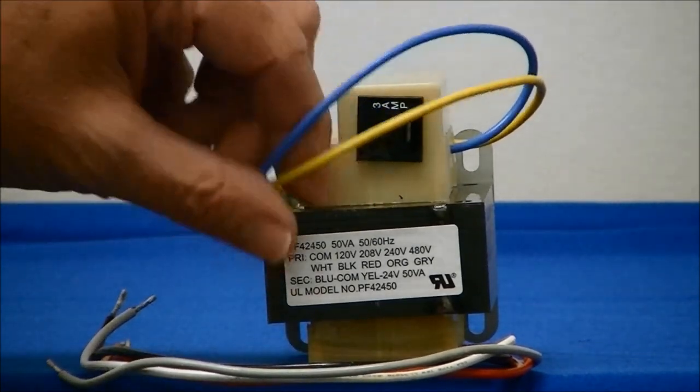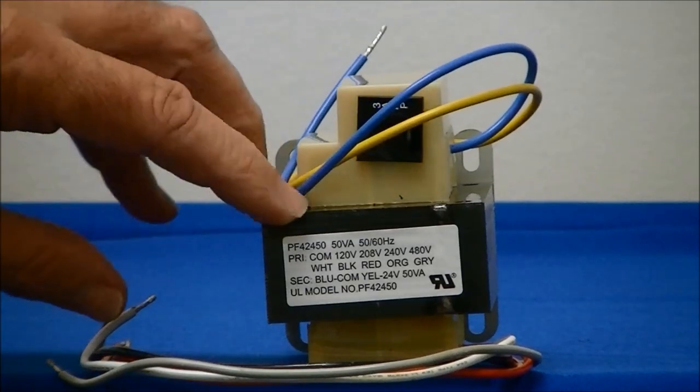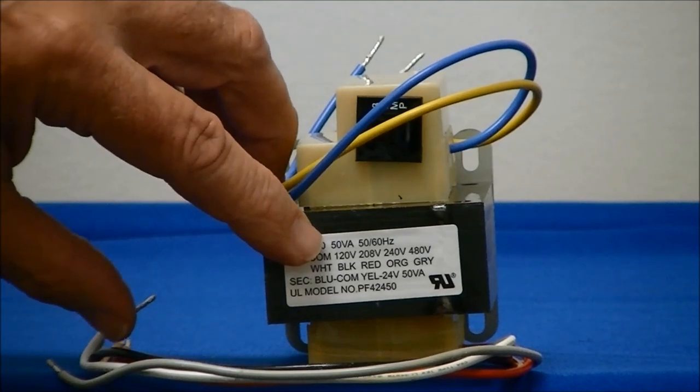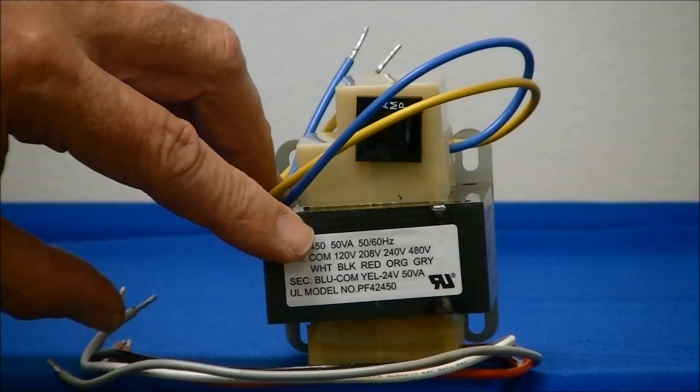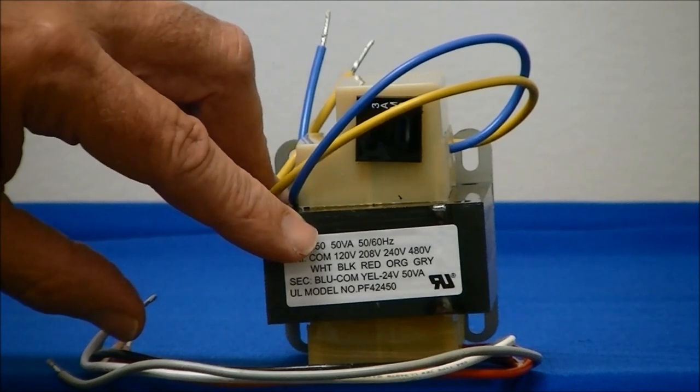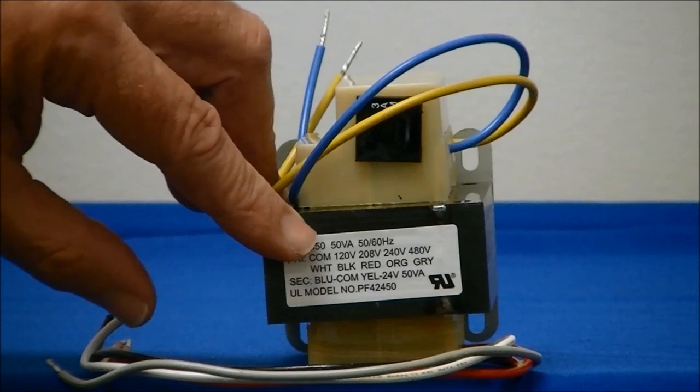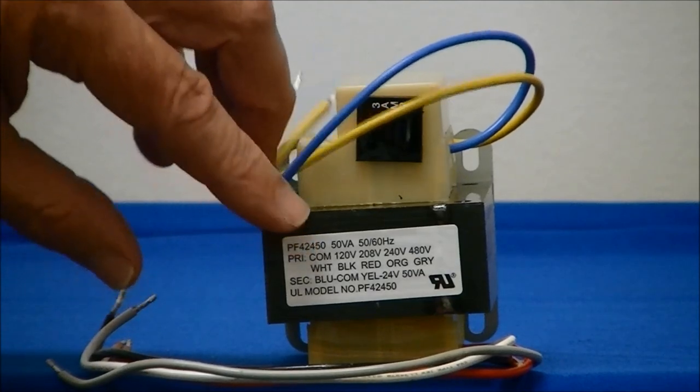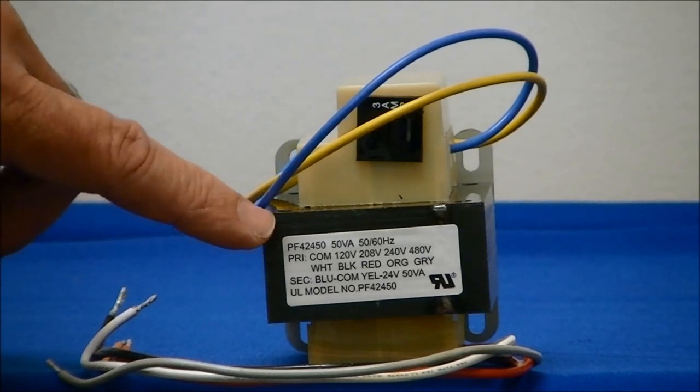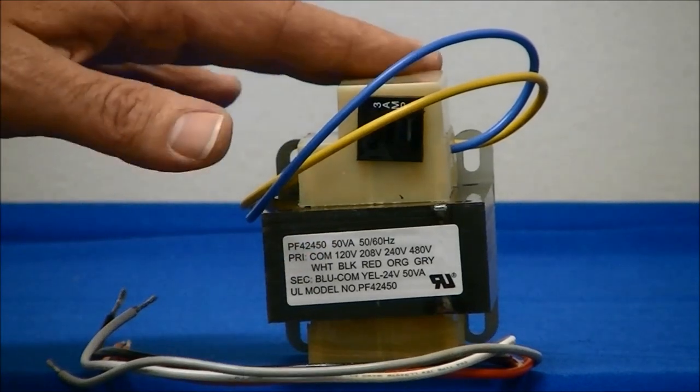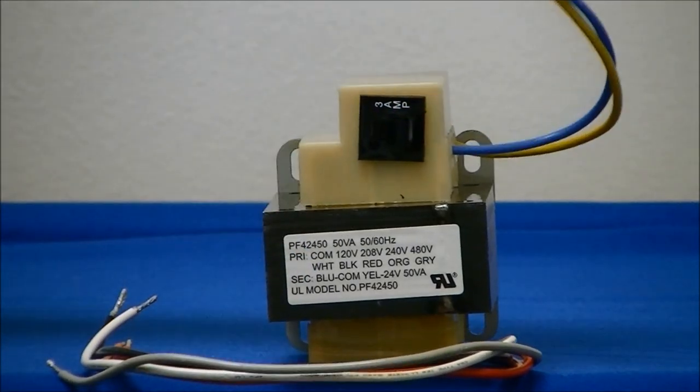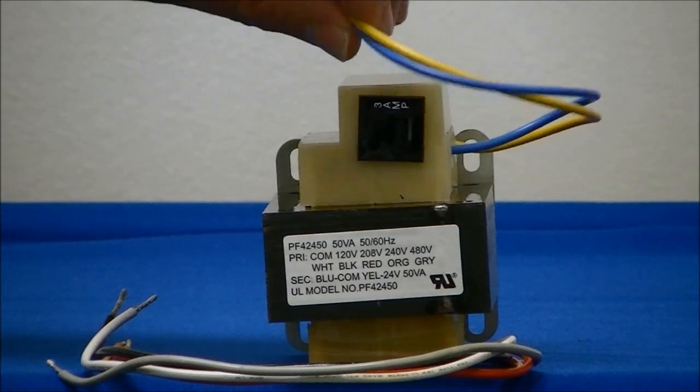On the transformer, this one is classified as a 50 VA transformer. That's 50 volt amps. The first transformer was a 40 volt amp transformer. So in addition to matching the voltages, it's important to match the load that the secondary voltage will be carrying. This particular transformer secondary voltage is 24 volts.